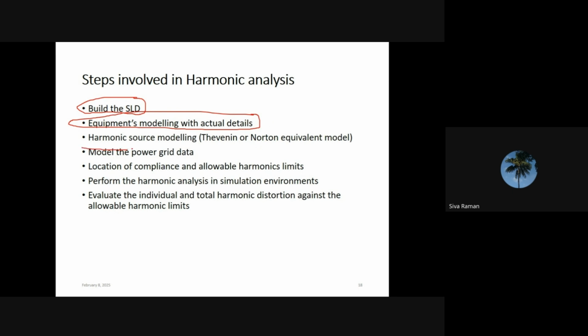Then the next one is the modeling of the harmonic source. In a solar plant or wind plant, the major harmonic source is the solar inverter, or the converter in the wind turbine generator, so that we have to model. Generally, we can model the harmonic source in two methods: the Thevenin equivalent or the Norton equivalent. In the Thevenin equivalent, we model the current harmonic spectrum as a voltage source with series impedance. In the Norton equivalent, we model it as a current source with parallel impedance. So this is an important step.